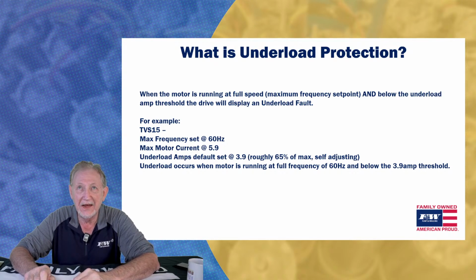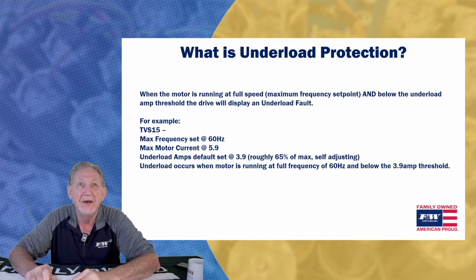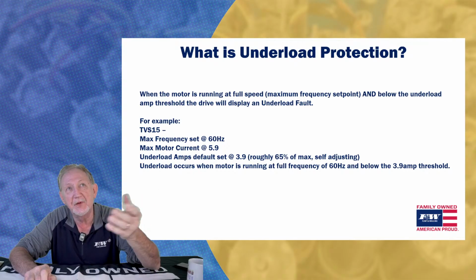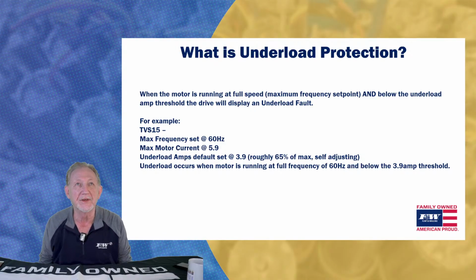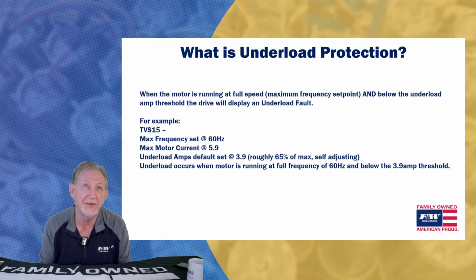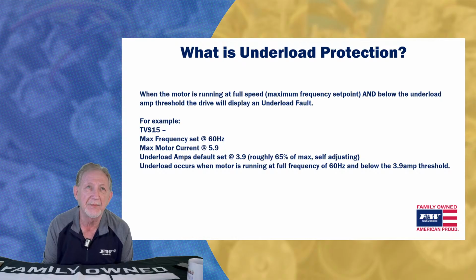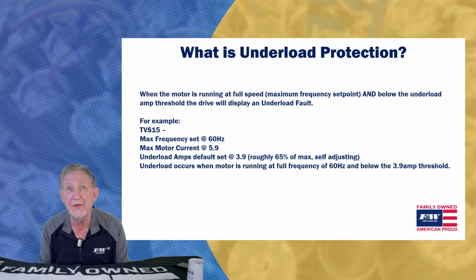And, capital letters, the underload amp threshold is below the underload fault, all right? So here's the example. You've got a TVS 15, that's a horse and a half. The max frequency is going to be 60 hertz. The max motor current on that, a three-phase motor, is 5.9 amps. So when that's been set up that way, the underload default is going to be 3.9 amps.